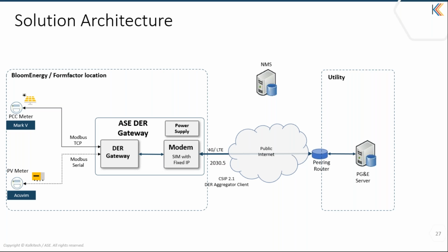And from there, we have a connection to the modem, and the modem exposes the gateway using a fixed IP. This is as per the PG&E specification that for whitelisting purposes, the modem needs to register to the PG&E server using a public static IP address. So we registered our modem into the network, and using the 2030.5 standard, the modem will be enabled with the certificate, and it will make connections to the server. Based on the whitelisting and firewall rules done in the server, it will allow connections from the modem. Since the whitelisting is done, it will make the connection, and from there we enable the communication through the 2030.5 channel.